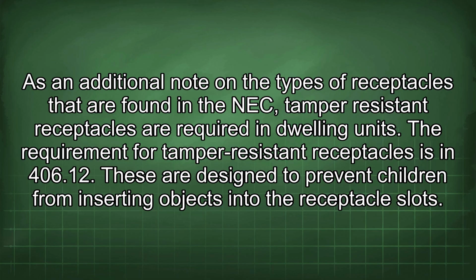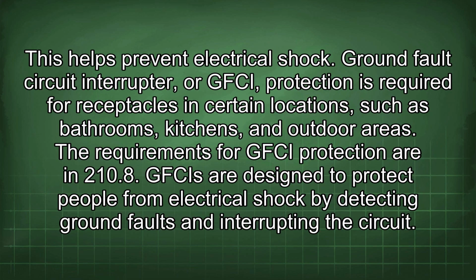As an additional note on the types of receptacles that are found in the NEC, tamper-resistant receptacles are required in dwelling units. The requirement for tamper-resistant receptacles is in 406.12. These are designed to prevent children from inserting objects into the receptacle slots. This helps prevent electrical shock.